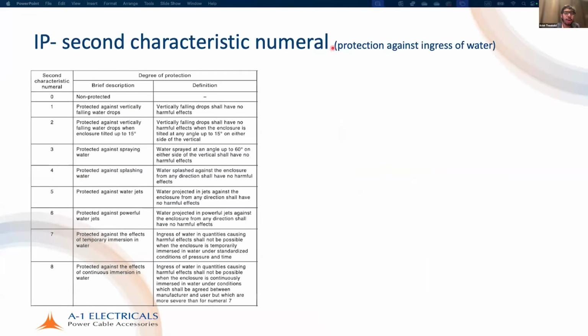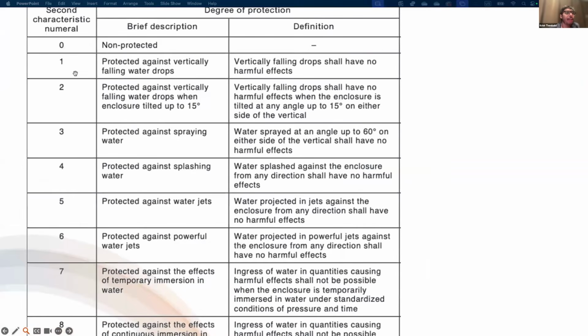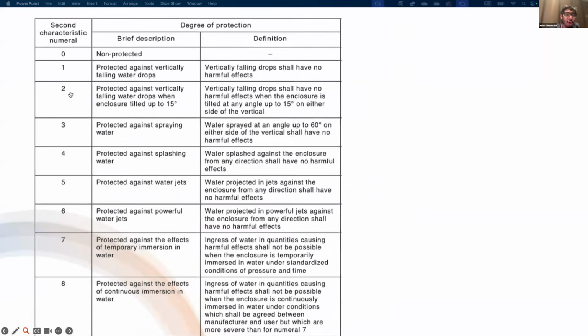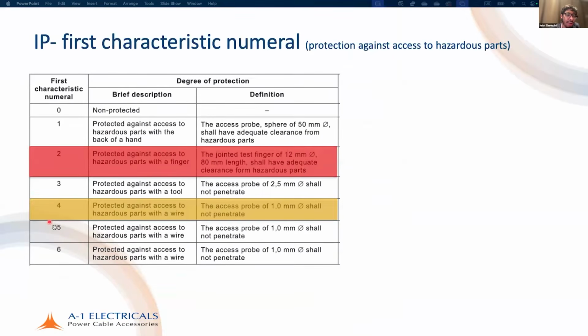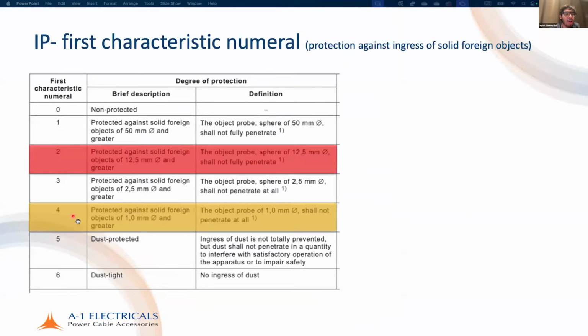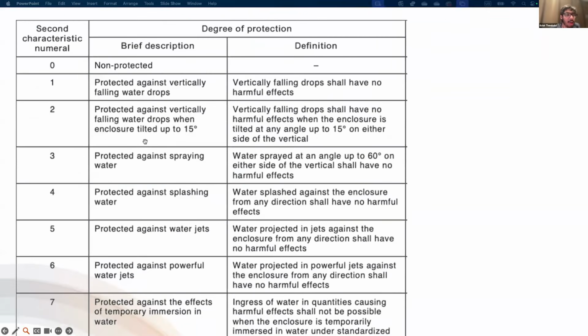The second characteristic numeral designates protection against ingress of water. So what are these? Now there are different types, as we know. 0 means not protected. 1 means protected against vertically falling drops. This is the second numeral. So IPX1, IPX2, whatever. X just means it could be anything else, or not particularly, it means not verified. But it could be, for example, IP44, or say for example IP42, the first numeral will be 4. So this 4 applies, and the next numeral will be 2. So it is this one that applies, for example.